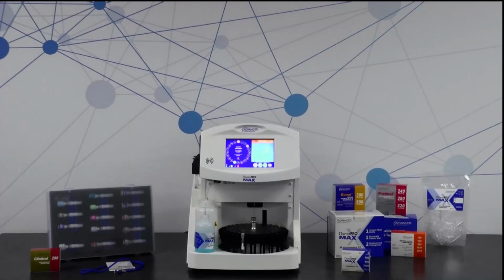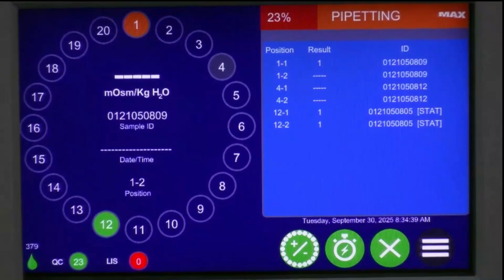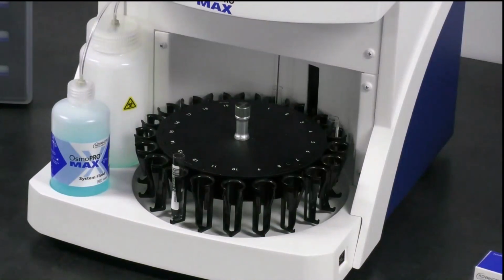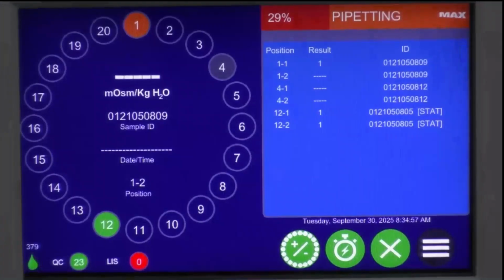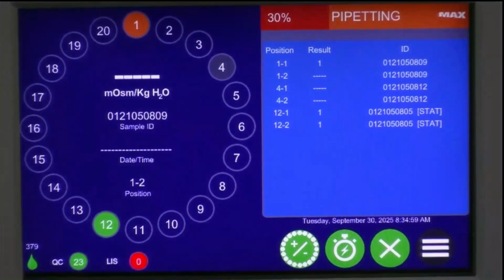Okay, so when you run each test, as it completes the test after it pipettes, you can actually see it pipetting here. If you want to take a look, you can see the little probe coming down into the tube and aspirating the sample, or the water in this case, which does have osmolality 1. So who knows what's been happening in there while it's been sitting around in the laboratory, in the demo room. But as we run each test, when it takes the measurement, you're not going to hear that loud banging noise that you did on the Osmo 1 or Osmo Pro, because there is actually no physical stimulus to nucleation. It uses a different technology for nucleation.